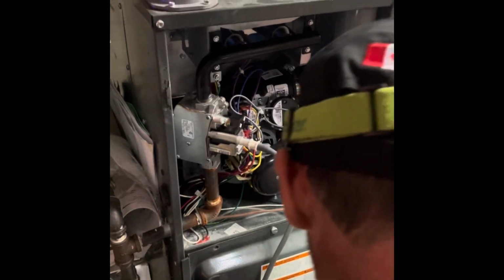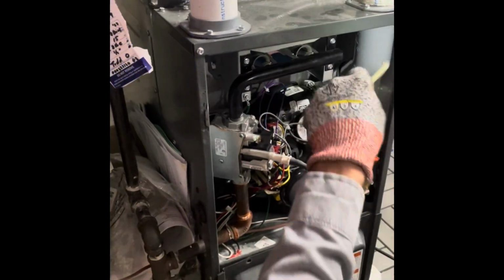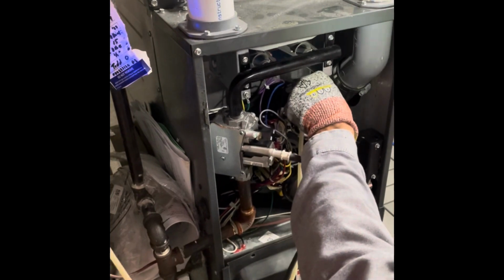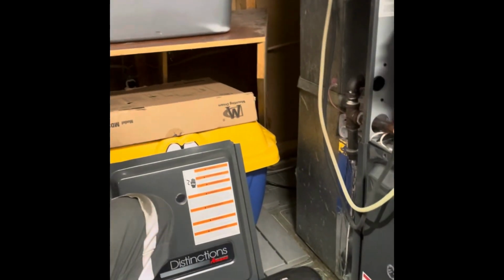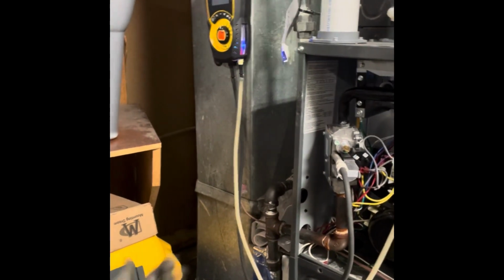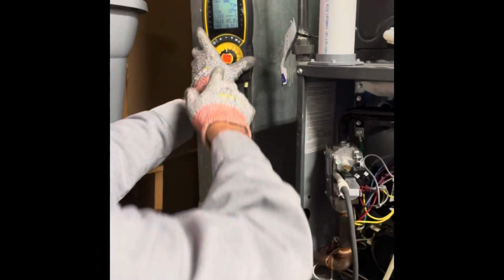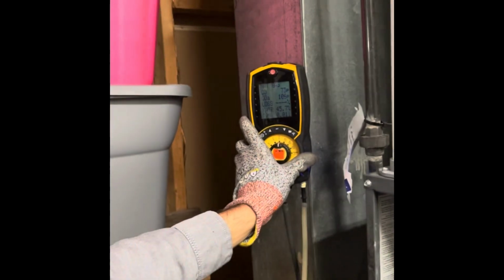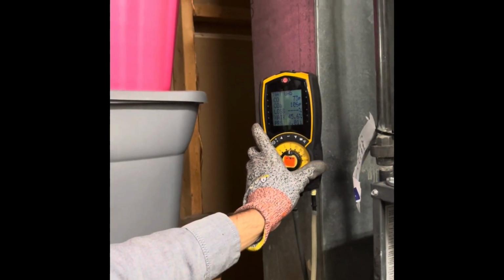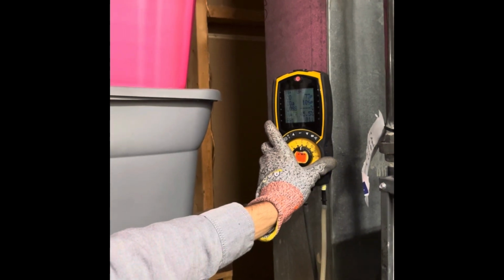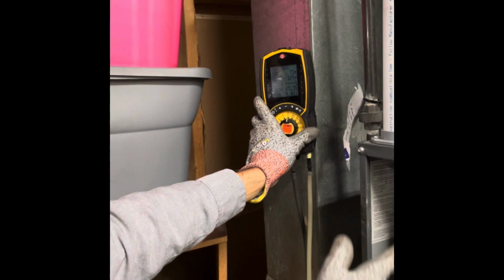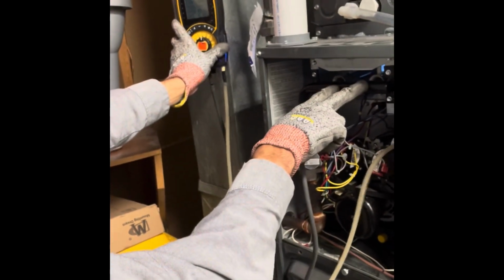Okay, so we'll just put that down. And now we'll start running this carbon monoxide test. If we look at our meter with this furnace, we can go up to 200 parts per million. Our meter is reading 72, 73. So that's a pass. If I were to have a reading over 200, I'd be making sure my gas pressure is set correctly, making sure our burners are clean, no spider webs in the orifices.